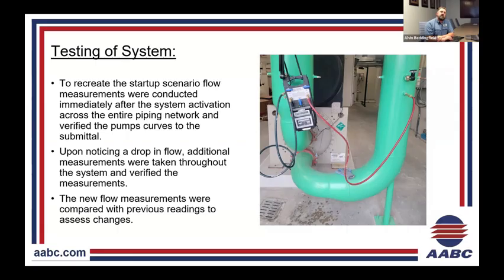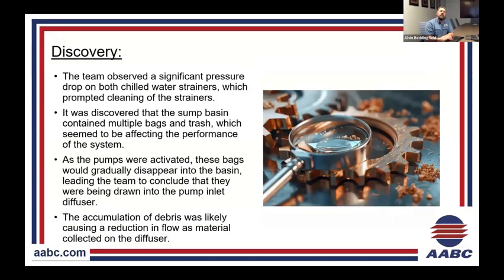So once the chillers started up and everything settled out, we left our devices on there and noticed the flow would completely drop. So we retook measurements across the pump curves and the chiller submittal. Once we collected that data, we compared the flow measurements to realize how much flow we had and how much flow we lost once that isolated low flow condition kept surfacing.